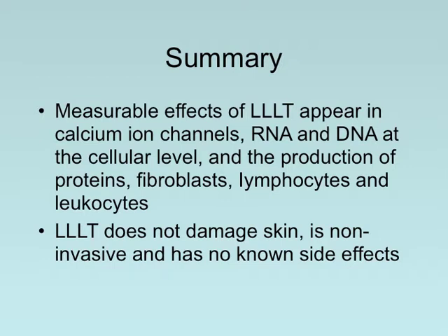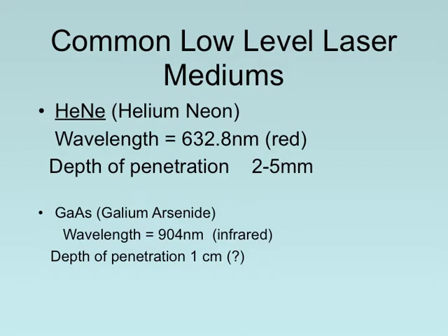Low-level laser therapy does not damage the skin, it's not invasive, and it really has no known side effects if used appropriately. Common mediums that are used, so we talked about this tube, and inside of it was a gas. The most common gas utilized is helium neon, which has a wavelength of 632.8 nanometers, and it appears as red. Depth penetration, the claims are that this laser can actually reach a depth of 2 to 5 millimeters, which really is about the depth level of the skin, just below the epidermis.